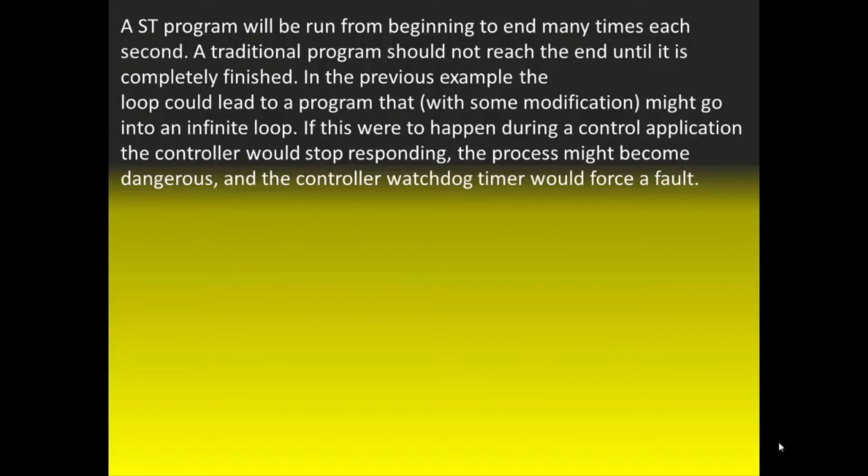A structured text program will be run from beginning to end many times each second. A traditional program should not reach the end until it is completely finished. If you're accustomed to writing text-based programs that actually sit and wait for certain conditions and don't keep executing all of the code, this is going to be a little bit different. You can't pause the processor for seconds, minutes, even hours waiting for some condition. In other words, there's a continuous task and it is continually executing something.